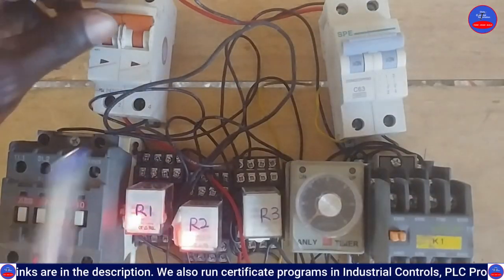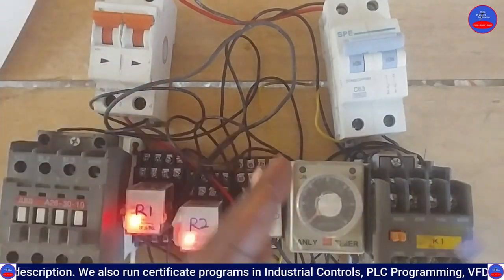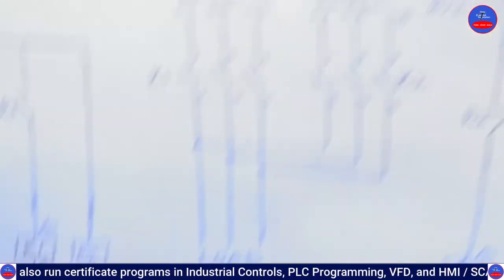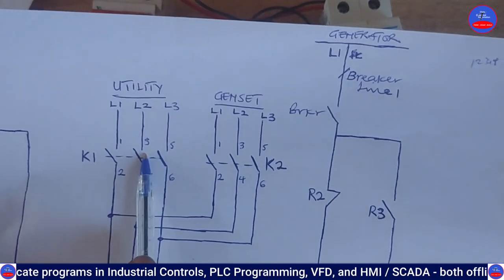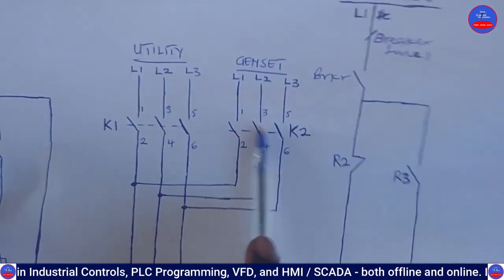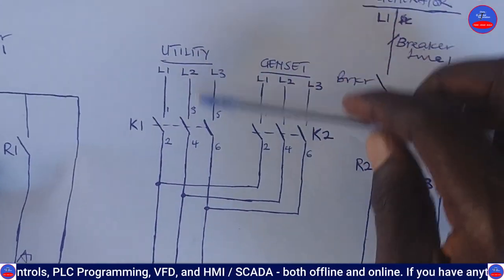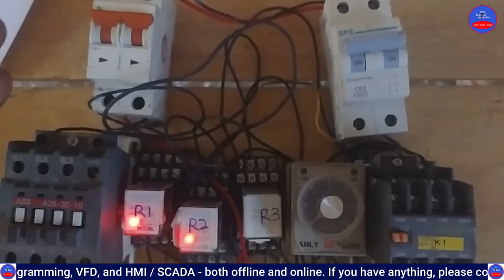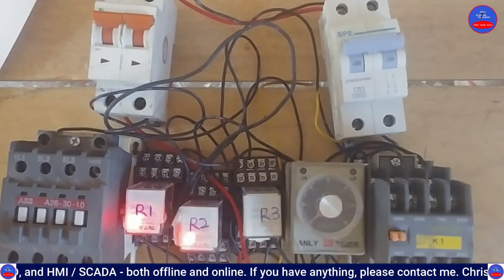So as the utility power was restored, the generator power is off. It means that this K1 is closed and this side is open, so that we are using the utility power.